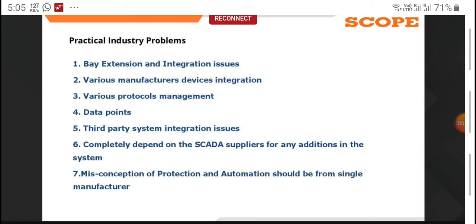So if meters are there, you have to add protocol converters. Some other meters, nowadays, are DLMS meters. So you again have to convert those protocols into the standard 61850 protocol if all the other relays are working on 61850. These are also a problem for the system and the vendor. Additional hardware is required to convert those things. So protocol management is also a problem.